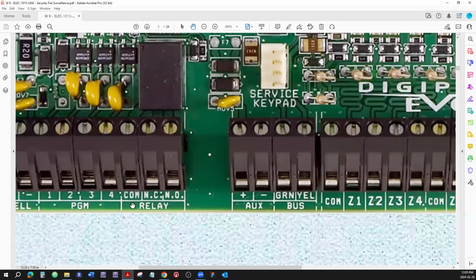Common is a common, so that would power something, either a relay or whatnot. These are the relay contacts, dry contacts—they don't give you any power, just a dry contact between this and common, or that and common. So it's a single pole double throw switch, a relay: common, normally closed, normally open.